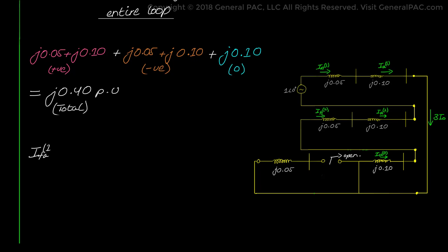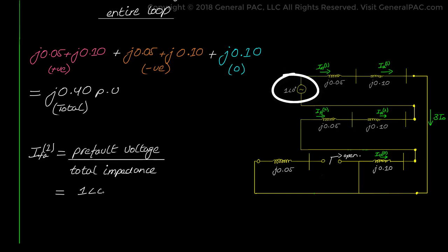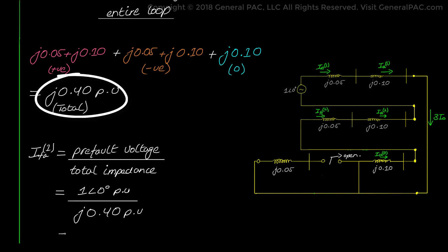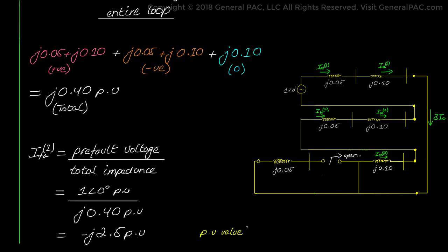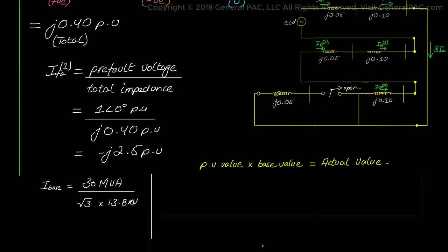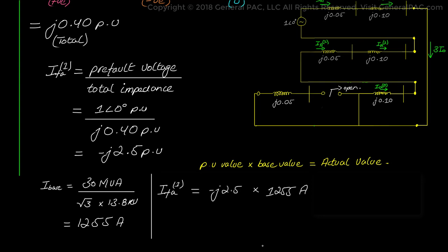The positive sequence current equals the pre-fault voltage of 1 per unit at angle 0 degrees divided by j0.40 per unit, giving us -j2.5 per unit. To find the actual current in amperes, the base current equals 30 MVA divided by the square root of 3 times 13.8 kV, which results in 1255 amps. Multiplying by -j2.5 gives us the actual positive sequence current of 3138 amps at -90 degrees.